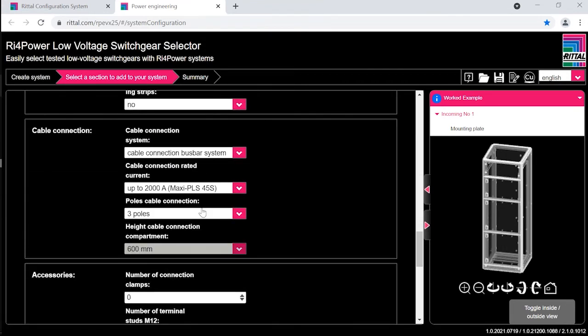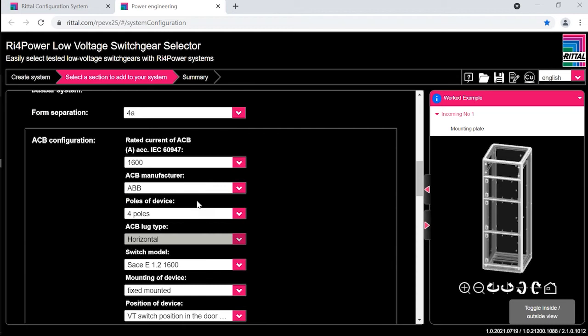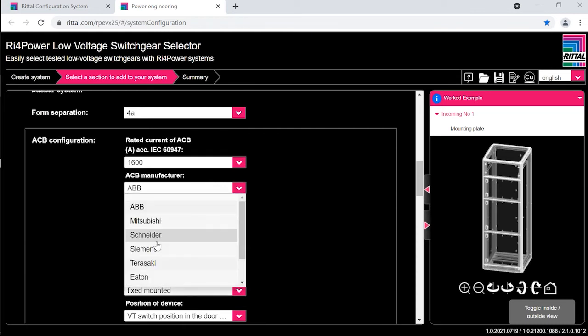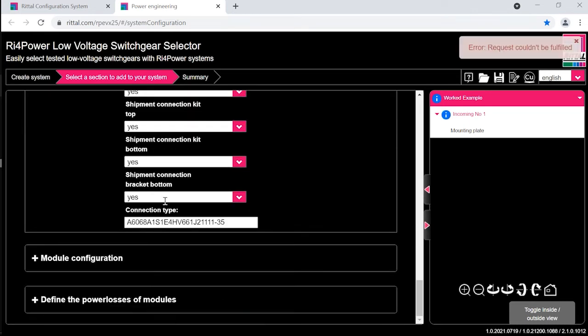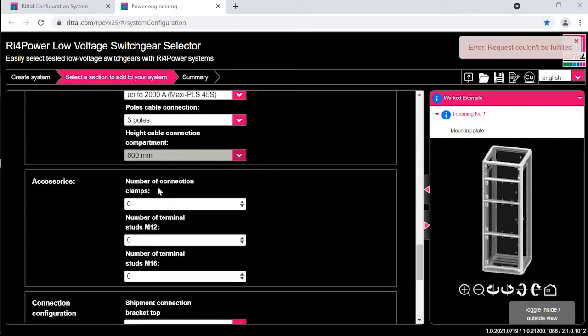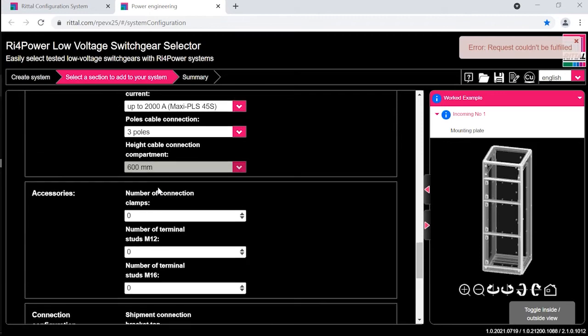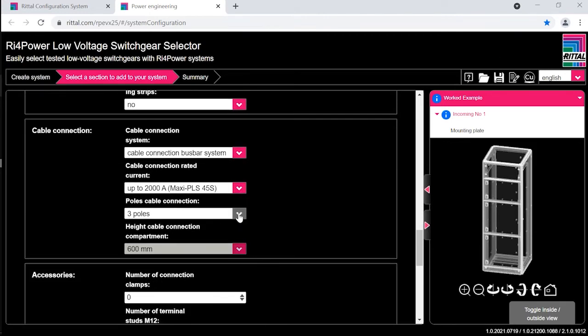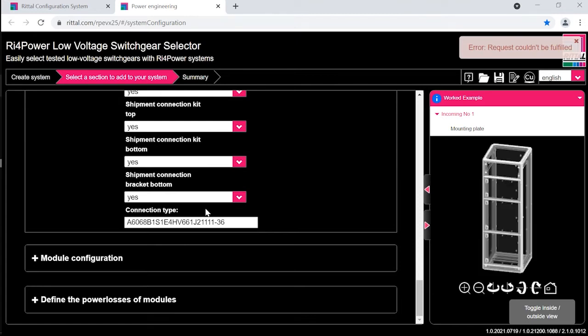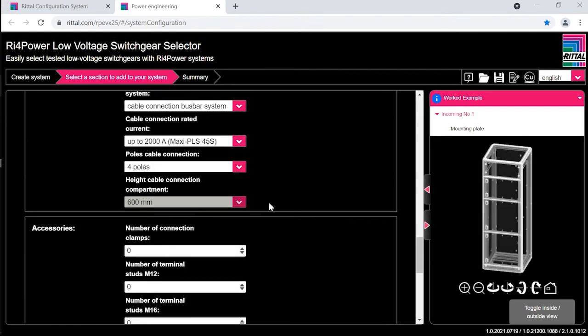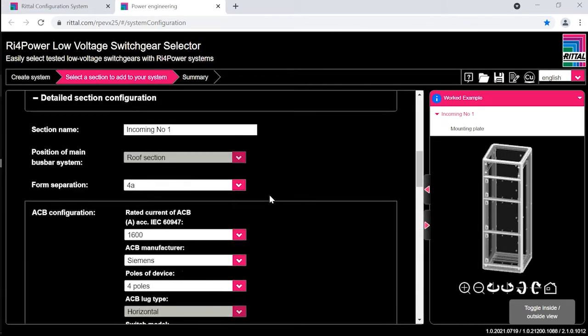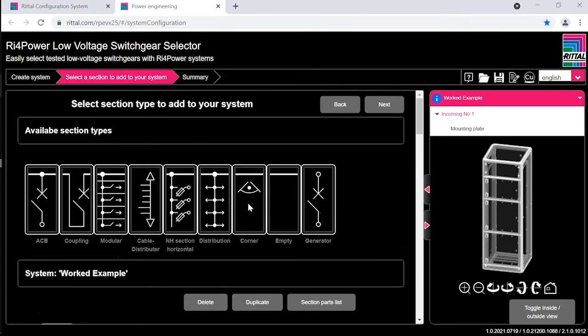Just scroll down again. Sorry. We will click Siemens, and there it will give you other options you can particularly select. So underneath the air circuit breaker, we're going for incoming busbar arrangement. That allows incoming cables to be connected to the ACB. That does make life a lot easier when you're connecting large incoming cables, for example. So that is the ACB section.